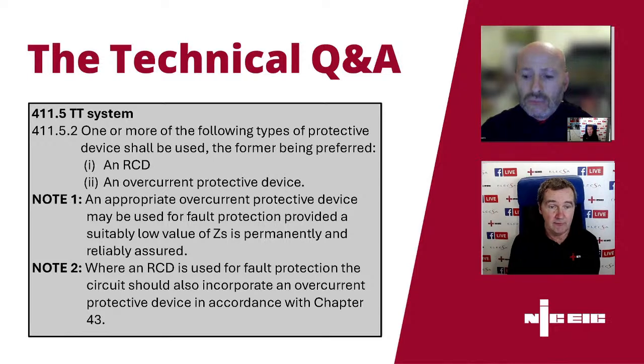I'm thinking that would be a typical scenario where you could do it, and that's reflected in Reg 411.5.2. That's one example where it is permanent and reliability is assured - you've got multiple earth paths going to ground, you're going to have a great reading, you're going to meet your disconnection times. The chance of it changing is very minimal. So that's the sort of example that would give someone the reassurance that yes, I can use that, as opposed to a more standard, smaller TT installation where you may not be able to achieve those ZS values.